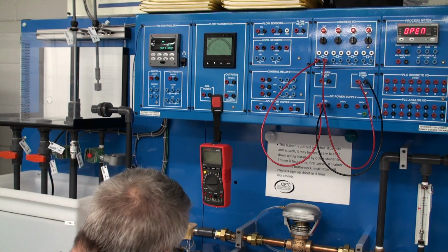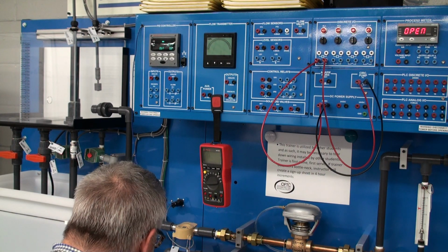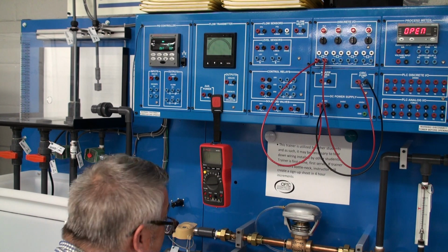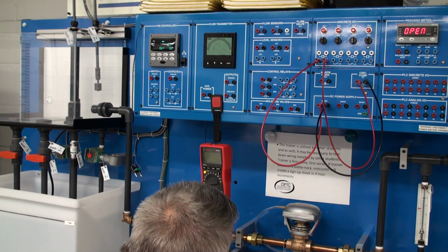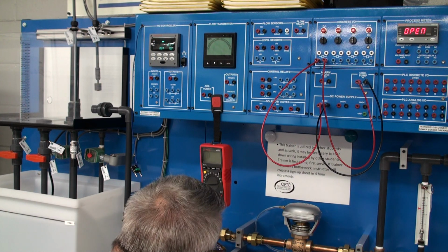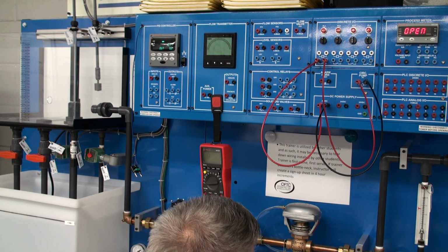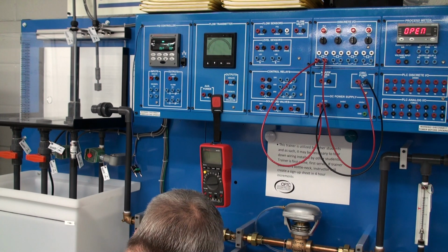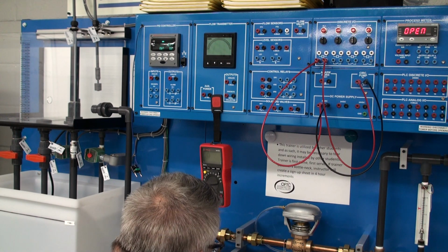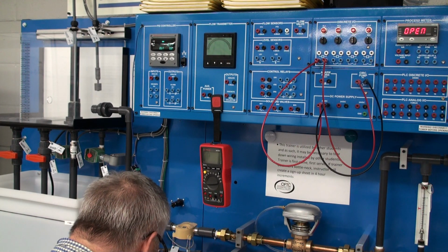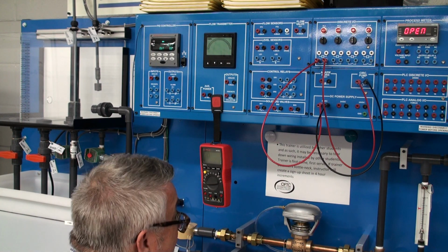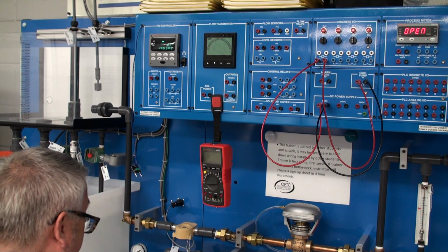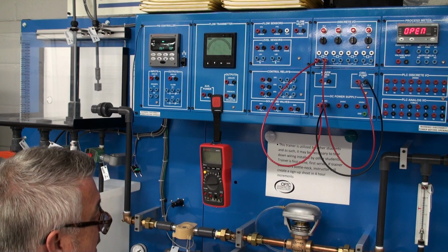So I'm going to turn the pump back on, and I'm going to open that valve by turning it counterclockwise to where we see this gauge get to 1.3 gallons per minute right here. So that's what we're going to be looking for. Excuse me, I think it's this gauge. I think I pointed to the wrong one here. Let me make sure I'm showing you the right one. Flow valve 100, yep, HFV. So that's this guy. And it's this gauge that we want at 1.3, so I was pointing to the wrong thing. So just trying to get ahead here.